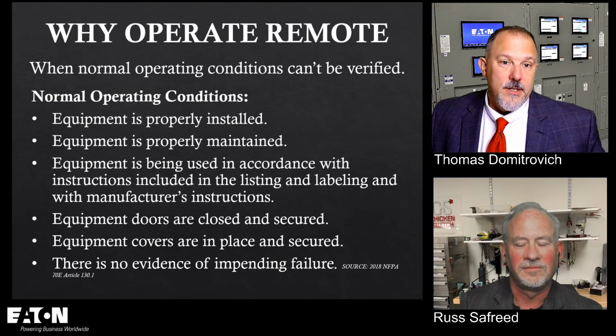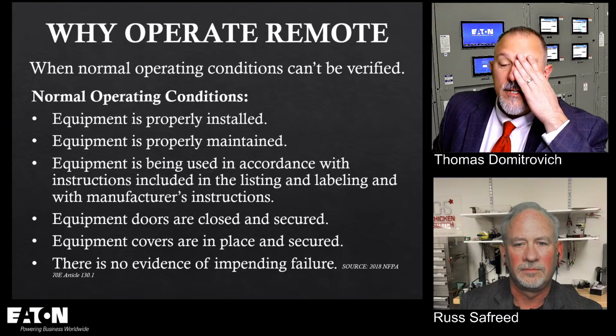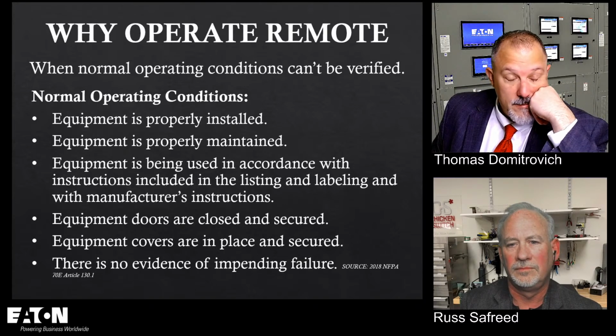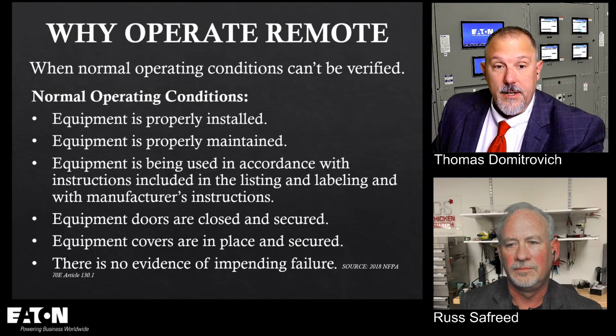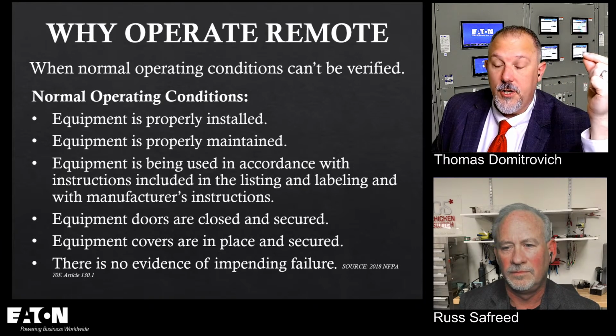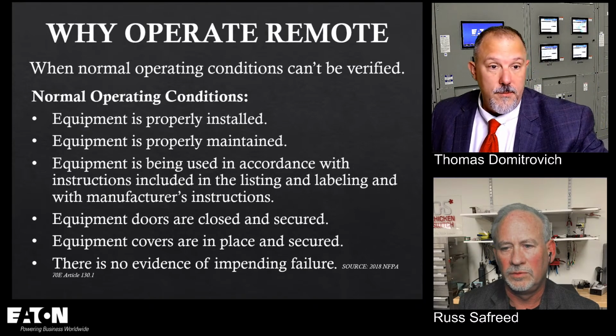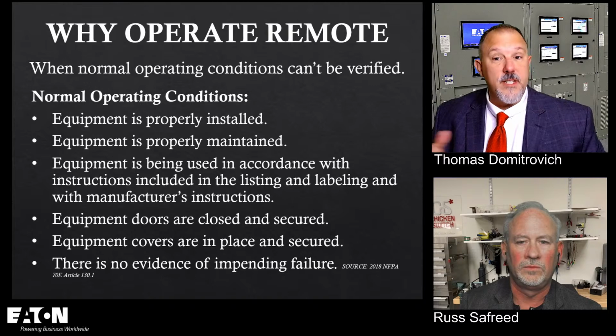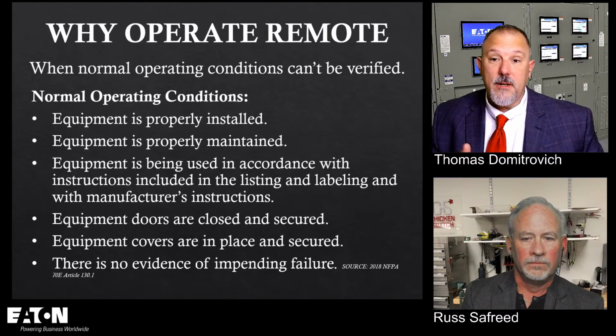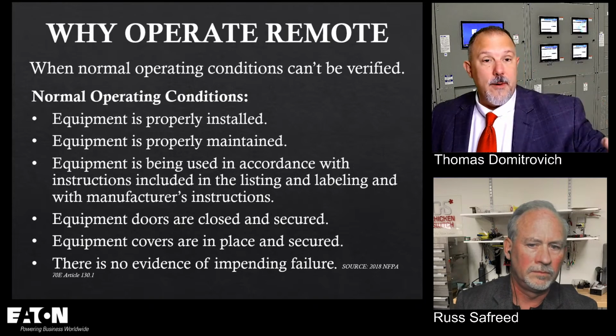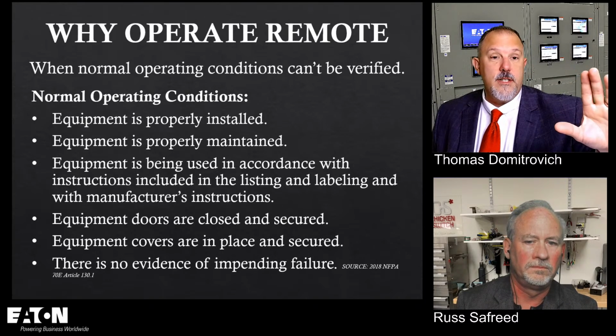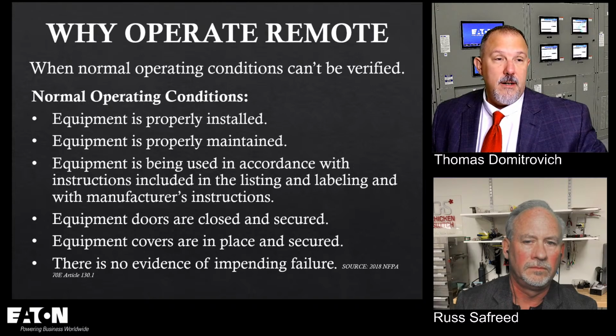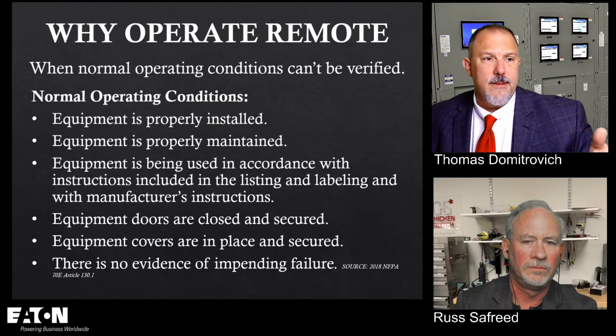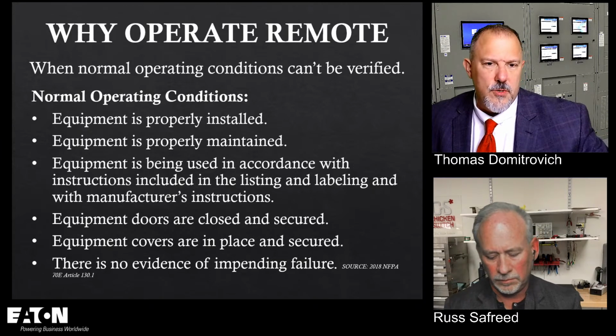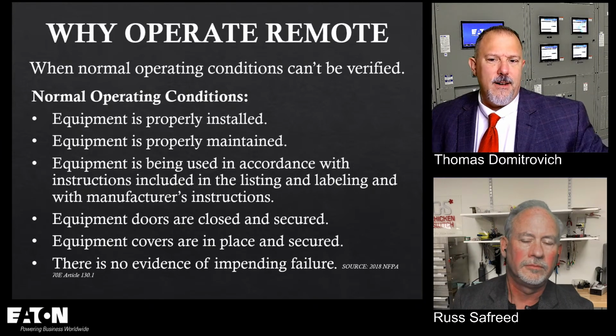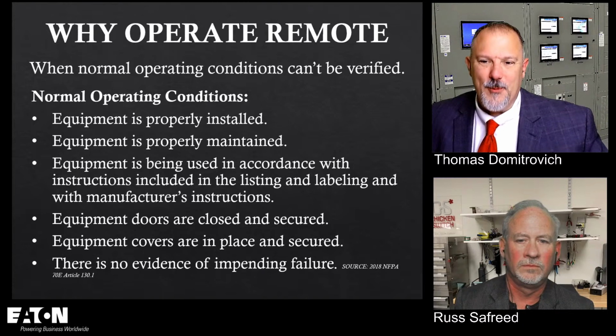That's right. It's almost as if, I used to hunt when I was a kid. I remember my dad telling me, you treat every gun as if it's loaded, and you always check it regardless of what anybody told you, because you've got to make an assumption from a safety perspective. In many cases, it's better to say, look, I looked at my records. I looked at the health of the breaker. I looked at the equipment, it looks in good condition. I looked at the available fault current that I estimated. It seems to be less than the short circuit current rating. I'm going to be outside the arc flash boundary anyway, right?